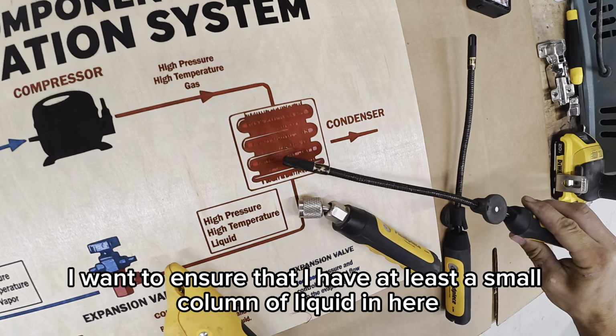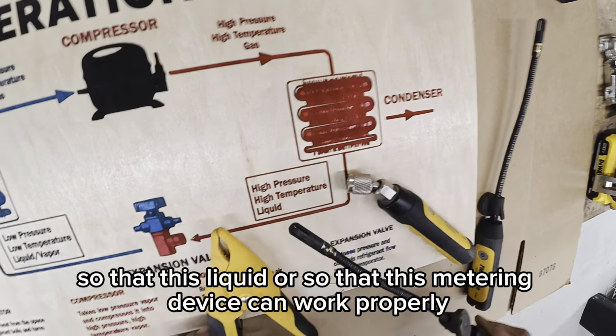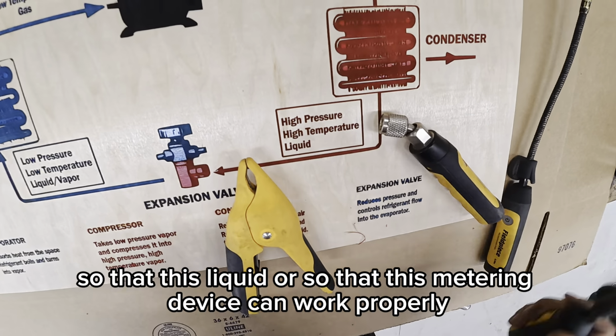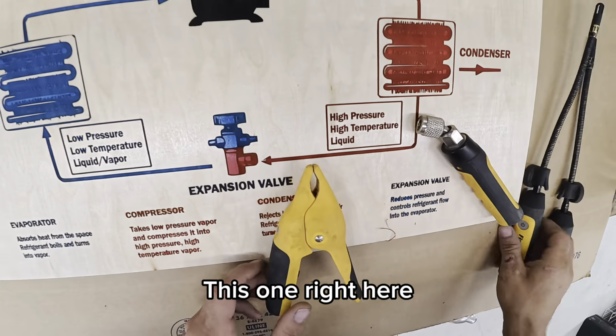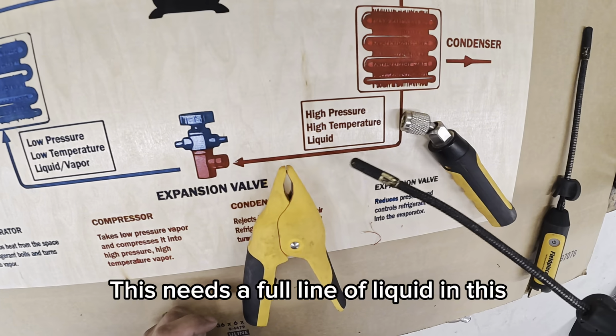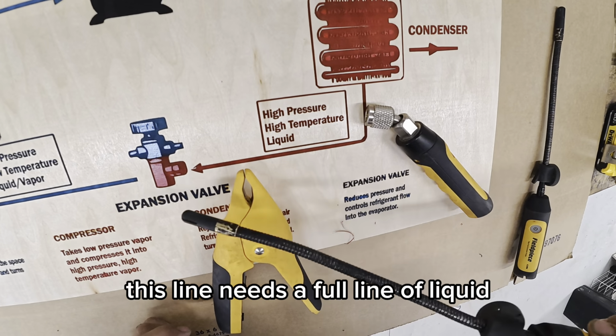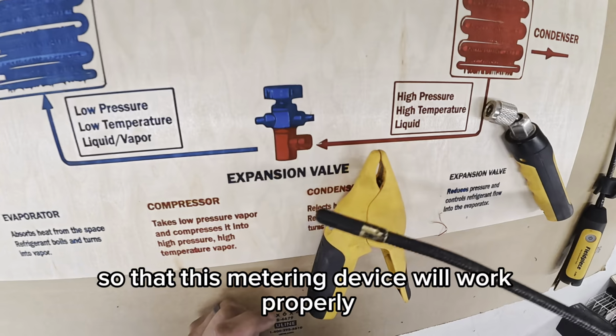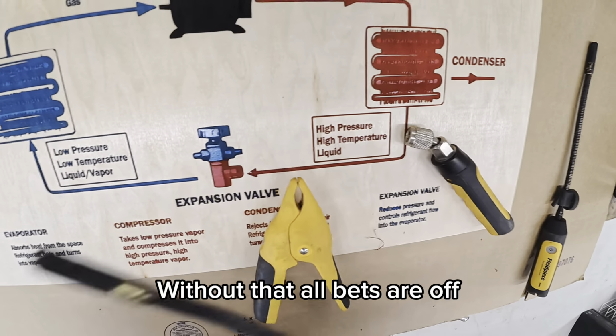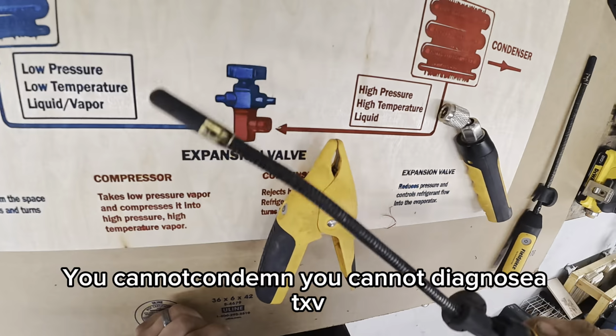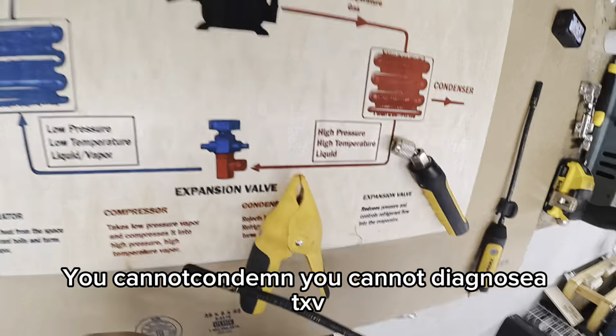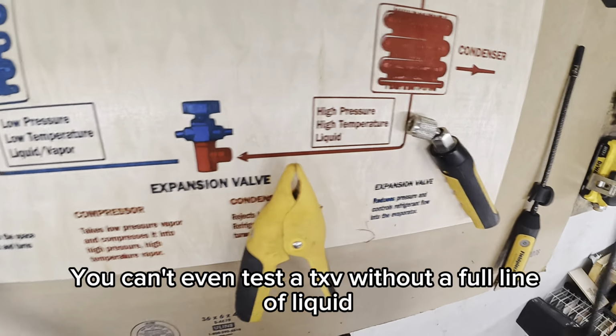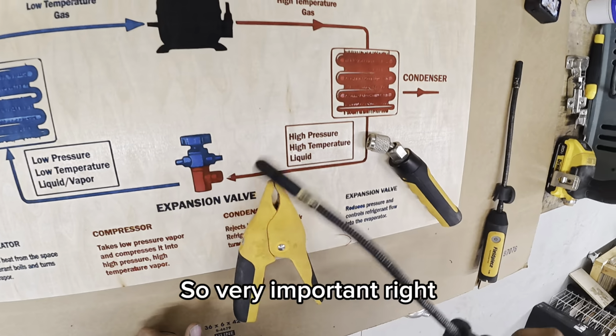I want to ensure that I have at least a small column of liquid in here so that this metering device can work properly. This one right here. This needs a full line of liquid, and this line needs a full line of liquid so that this metering device will work properly. Without that, all bets are off. You can't diagnose a TXV, you can't even test a TXV without a full line of liquid, guys. So, very important, right?